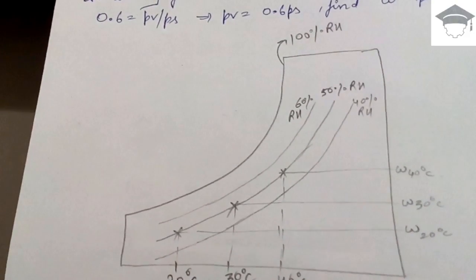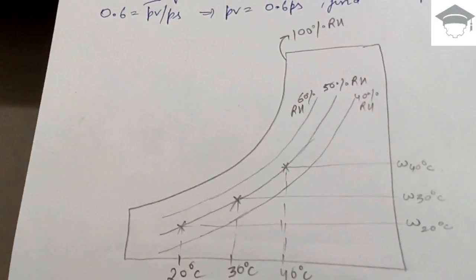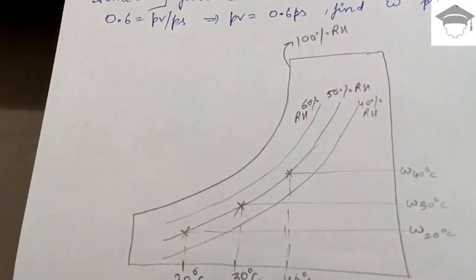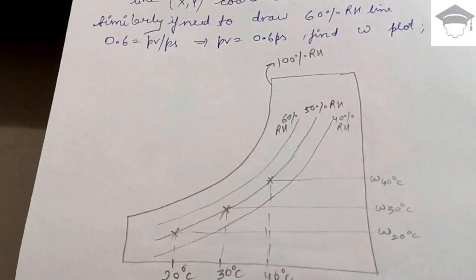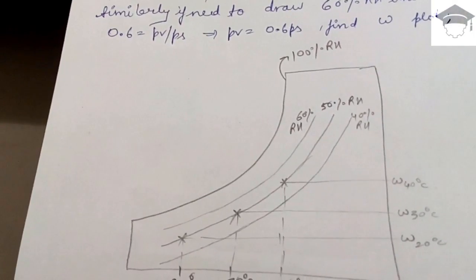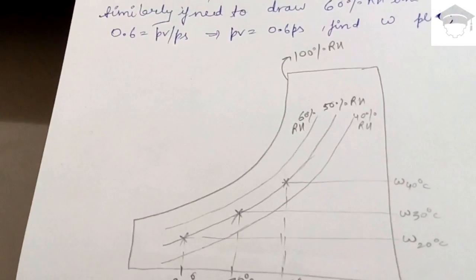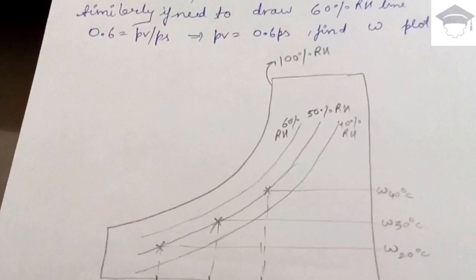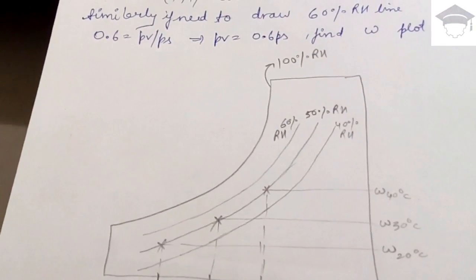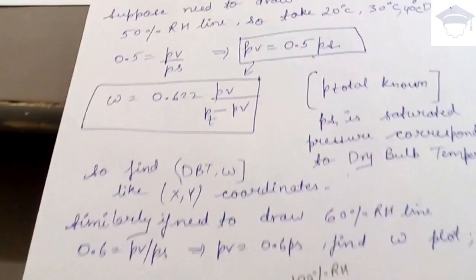Similarly, to draw 60% RH, 40% RH, or 30% RH lines, use the formula φ = PV / PS with the respective phi value — for example, put φ = 0.6 for 60% RH to get PV = 0.6 × PS. Then find omega, locate the DBT and omega coordinates, plot the points, and join with a smooth curve to represent the relative humidity line.